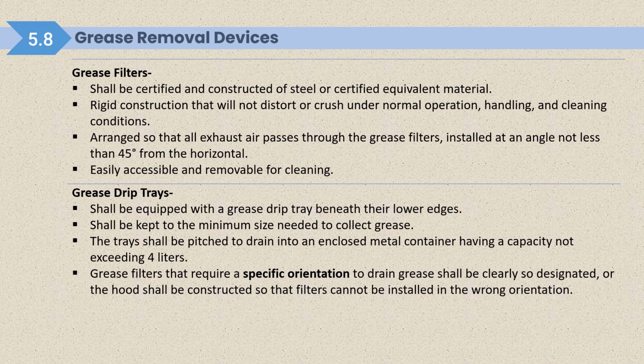The tray beneath their lower edges shall be kept to the minimum size needed to collect grease. The tray shall be pitched to drain into an enclosed metal container, and that tray should be pitched in such a way that it will drain the grease into a container having a capacity not exceeding 4 liter. Grease filters that require specific orientation to drain grease shall be clearly so designated, or the hood shall be constructed so that filters cannot be installed in the wrong orientation.